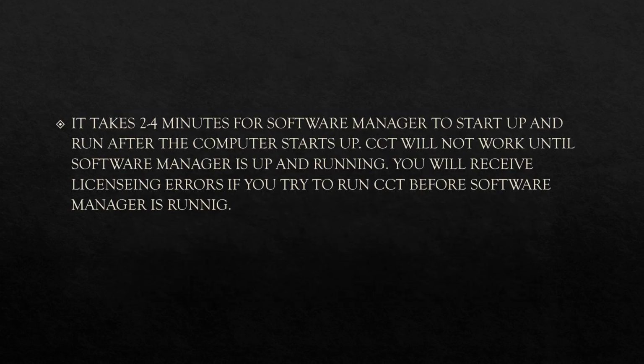So it takes 2 to 4 minutes for Software Manager to start up after you run your computer. Now this is somewhat true, and there is a workaround here. If you go to your Windows key and type in services and go down to JCI license service, when you double click on that, you'll see it's a delayed start. If you want it to start up instantaneously with your computer every morning, you can change that delayed start to automatic and you're good.